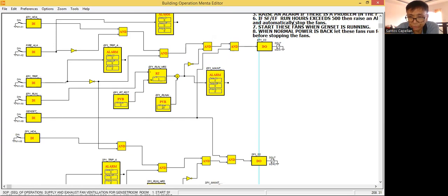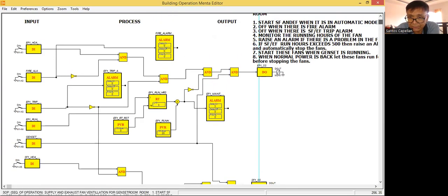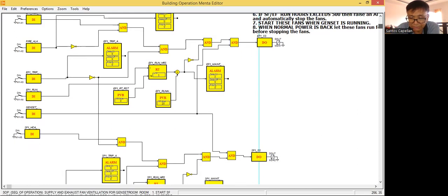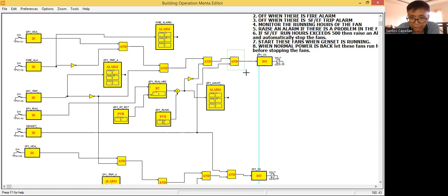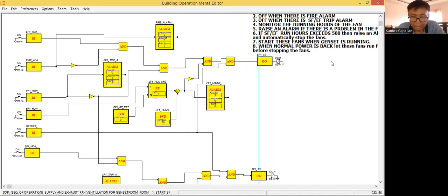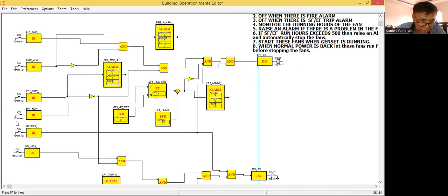So that will be the start of these fans when the generator set is running. Don't forget to still include the logic above. So from one to six, it should be considered also. Then when normal power is back, let these fans run for another five minutes. So what you need to do here is create a delay — because that is the challenge.